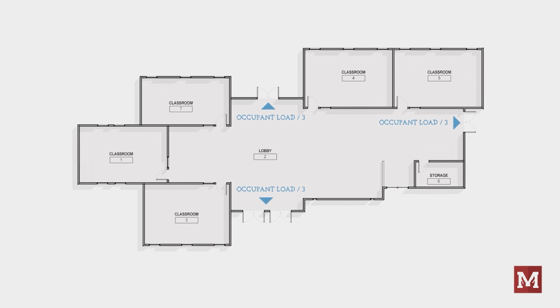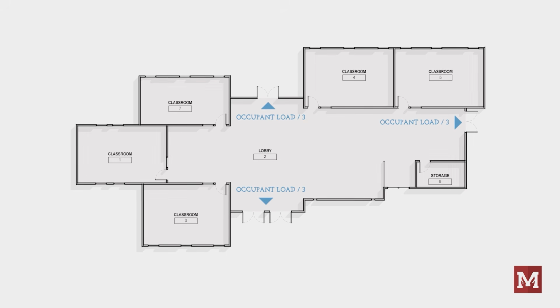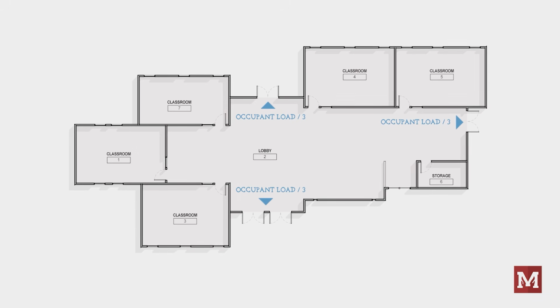My recommendation, first divide the occupant load by the number of exits and see if there's enough capacity. If this works, you're good. The more complex method is technically correct, but I would only use that if the first method doesn't work out.